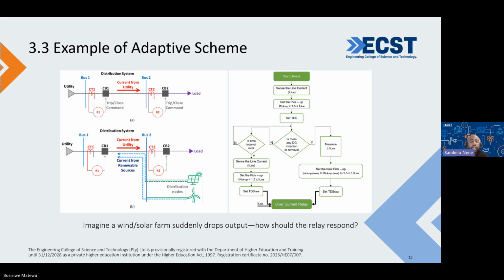Looking at the second example, B, now we have bidirectional flow. After the second bus we have distributed sources - solar panel and wind. We see current coming from the utility, shown in red, and also current going upstream. So we have current going downstream and current going upstream - bidirectional flow. A traditional relay wouldn't be able to pick up, or it might misoperate or misidentify the current coming from downstream. Hence we need adaptive relays that are able to pick up that flow going upstream.